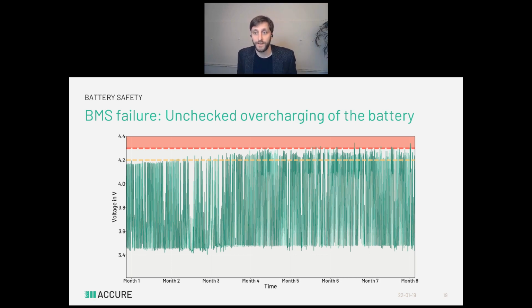By the way, this is historical data that we got, so we would have ended the operation much sooner if we had monitored something like this live. Moving on to months 4, 5, and 6, almost every day the upper voltage limit is beyond what the cell is specified to. Towards month 7 and 8, you can even see the battery going to 4.3 volts, which is not a reason to start running away right now, but it shows there's a systematic error with this cell and with this whole system. If something like this goes unchecked, there might be other things we should worry about.